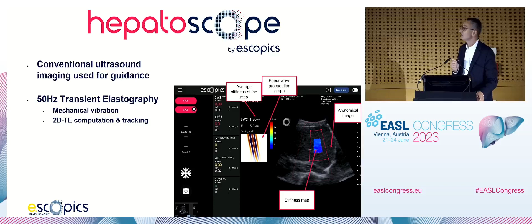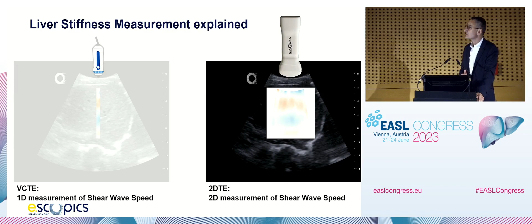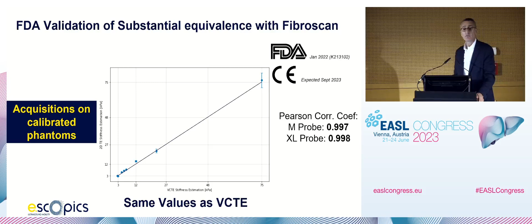So that's the first difference with the well-known FibroScan. The other thing is that, of course, you know that you are in the liver, which unfortunately is not the case when you have a single element. This is an FDA-cleared device, and the FDA has broadly validated the measurements that this device is capable of doing. It's no surprise that the measurements correlate exactly with what FibroScan is doing, for both the M and XL probe, whereas hepatoscope has only one imaging transducer.